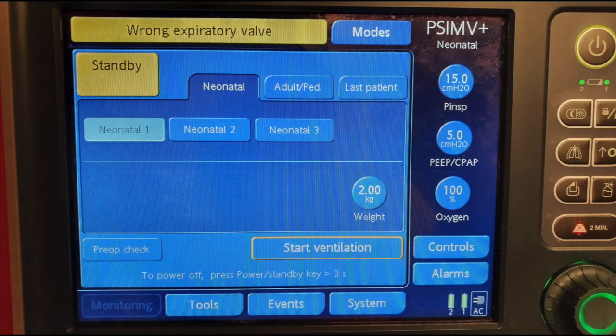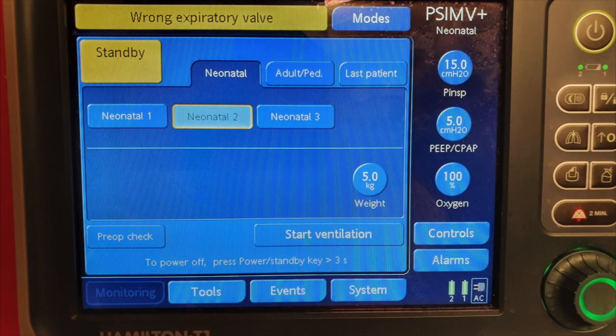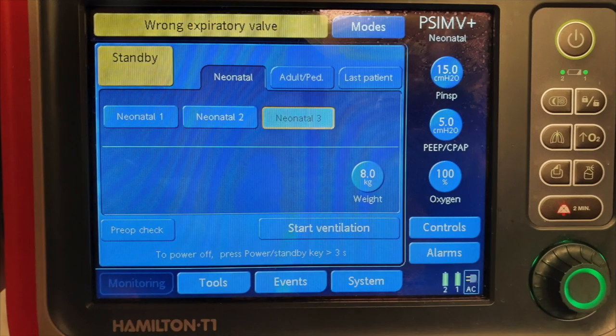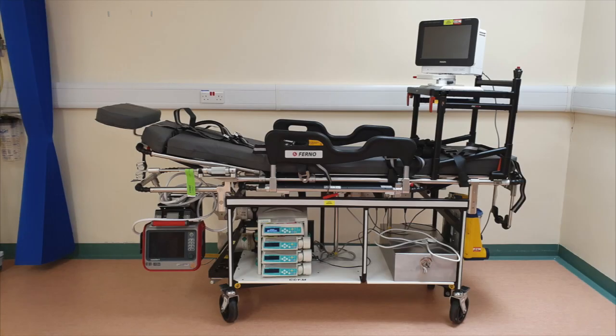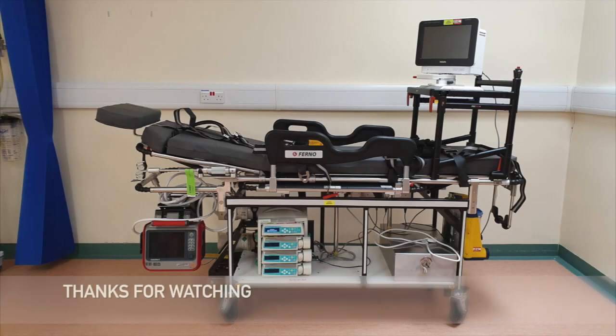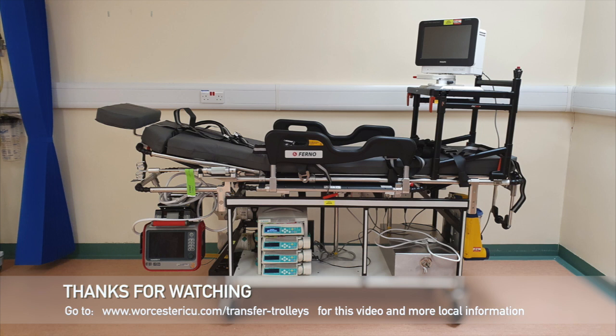At setup, the neonatal setting should be chosen, and a number of default weights are pre-inputted for children of 2, 5 and 8 kilos in a pressure control mode. These can be modified to match the child's weight. You can see in these pictures that the machine has recognised that an adult circuit is attached and displayed a warning. To see a detailed setup of the complete Ferno Transfer trolley and Hamilton ventilator, see the accompanying video.